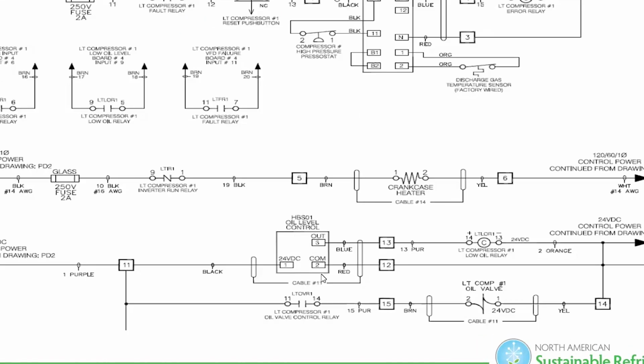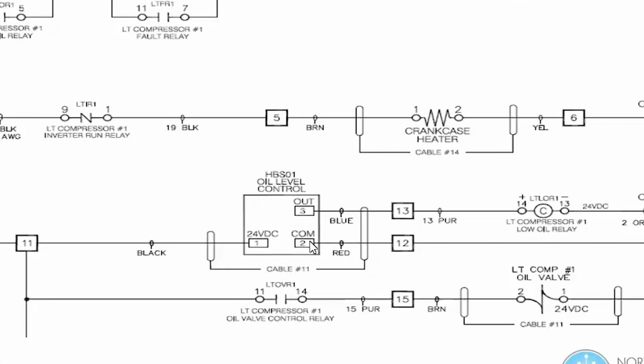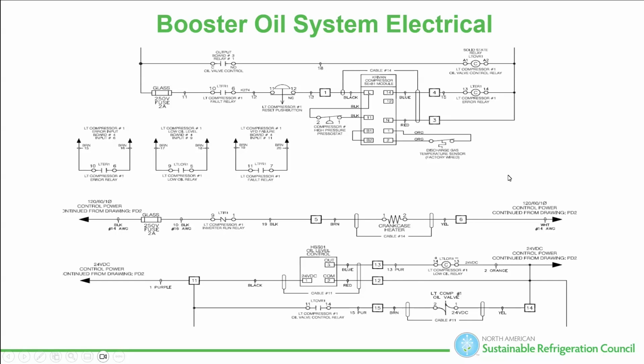So here we go. Oil switch. This is good, that means I'm running. But now I need oil. I'm going to close that switch 1 to 3, passing 24 volts DC to this coil. So the first thing I would start, where does the circuit start? It starts with the sensor or the switch. So that's where I'll start, because we're doing the order of operation first. And then what is that going to do? That's going to energize this low temperature compressor oil relay. How do I know? It tells me it's LTLOR1.